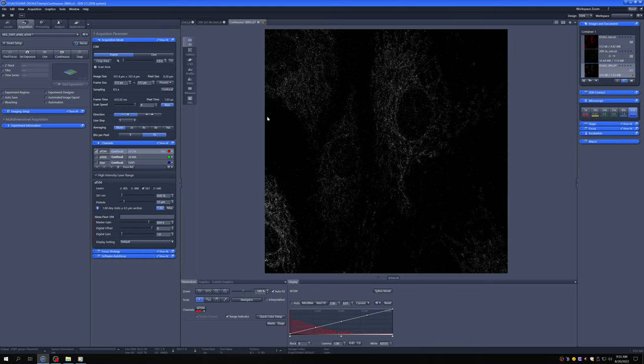Now you might be asking yourself, why would you do averaging at all? Because I've already shown you a different way of improving the quality, which is to lower the gain and increase the laser power. What are the trade-offs? If you increase the laser power and lower the gain, you get higher quality but you will get higher bleaching because you have a higher laser power. If you increase the averaging, you will also get higher bleaching because you're imaging the sample two times, four times, eight times or 16 times. But in addition, it will take longer. It doesn't take longer if we increase the laser power.